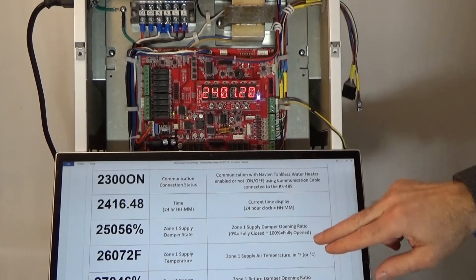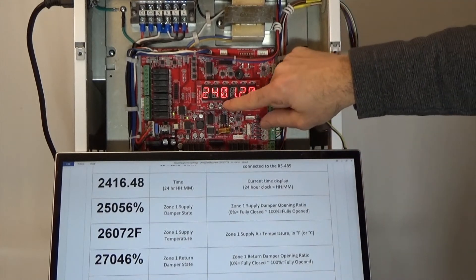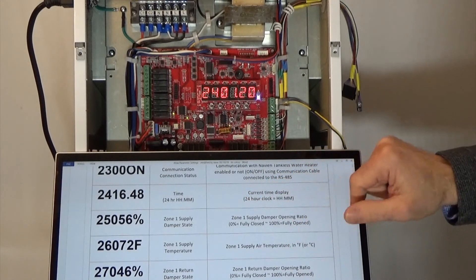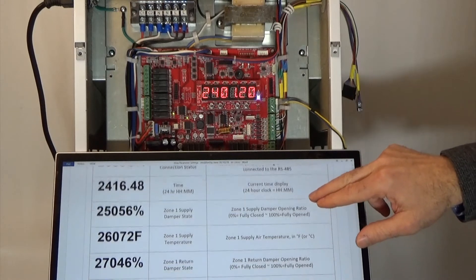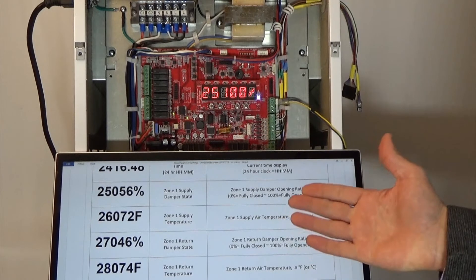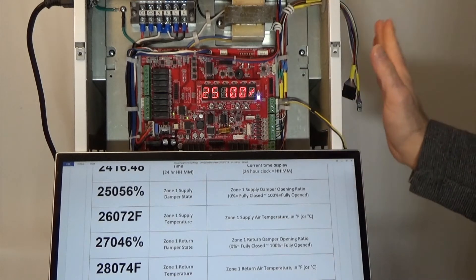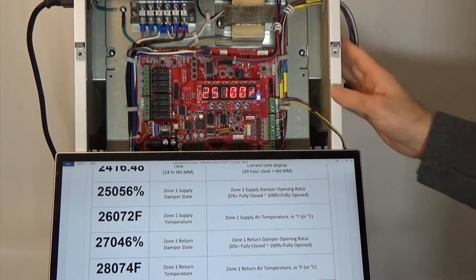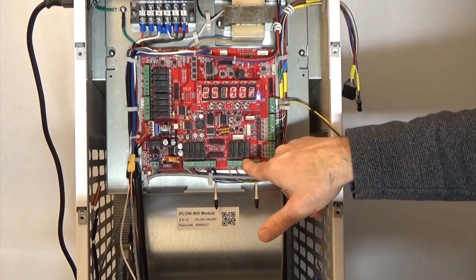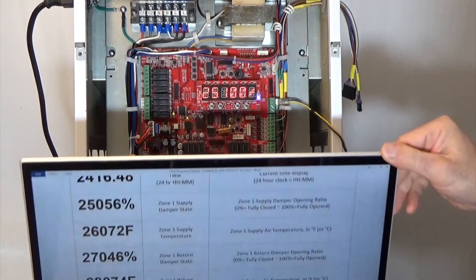Parameter 24 allows us to set the date and time — it sets the 24-hour clock on the unit. Starting at parameter 25 through 40, we are looking at the conditions of the zoning system. This is a two-zone system. You can see we have two zones worth of dampers connected and two thermostats connected — those are our zone relays.